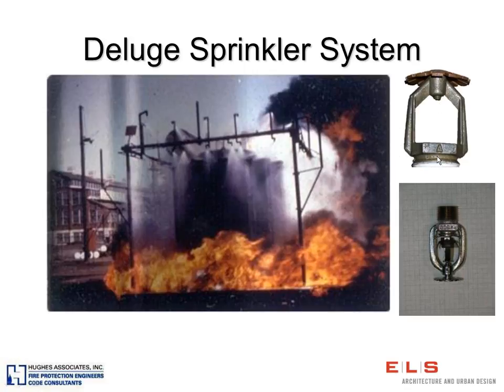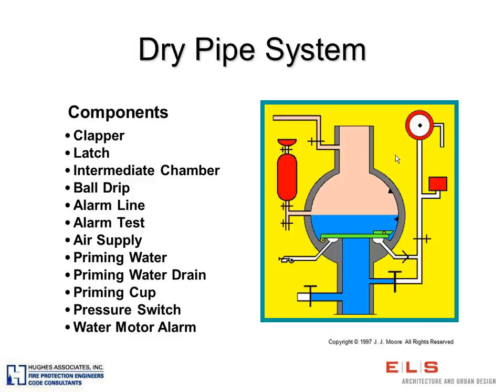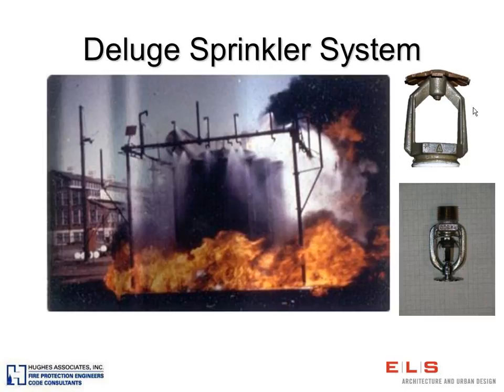Everything is open. So just like this picture, there's water below a valve and there's nothing above it. However, because the sprinklers are open like this, we cannot maintain air under pressure. So for the deluge system valve, you actually need a detection system around it. There's usually a heat detection system around this that would trip the valve.